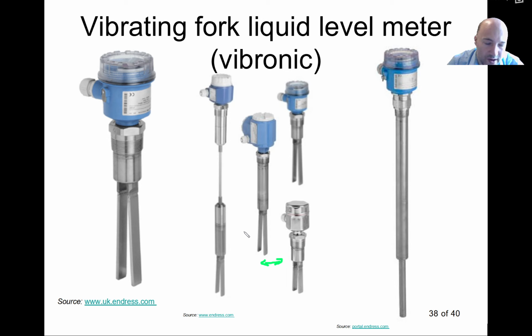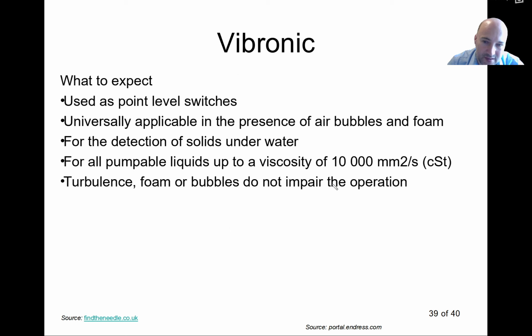It is also very reliable. You can see that basically the only moving part is the very slight vibration of this, which is very small, and there's no problem with that. So what can you expect? Well, this works also if you have air bubbles and if you have foam. It can also detect solids underwater.